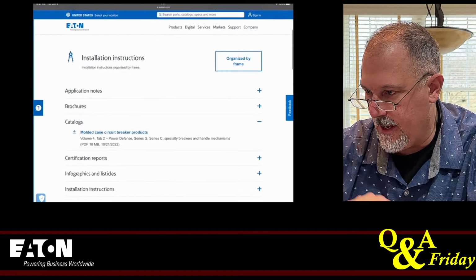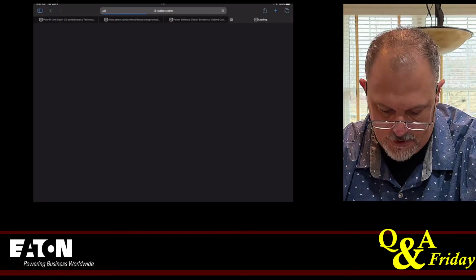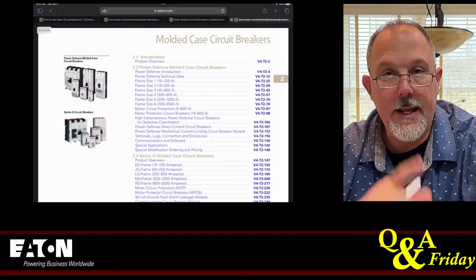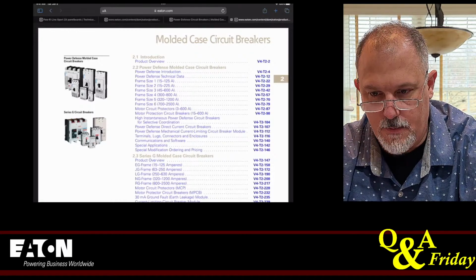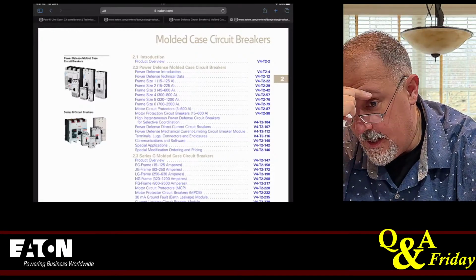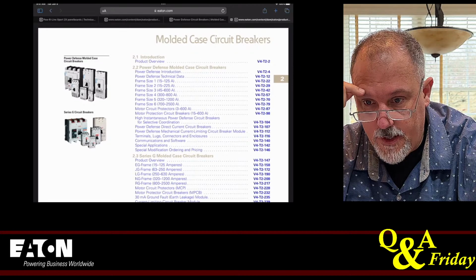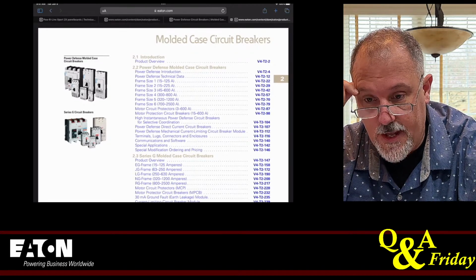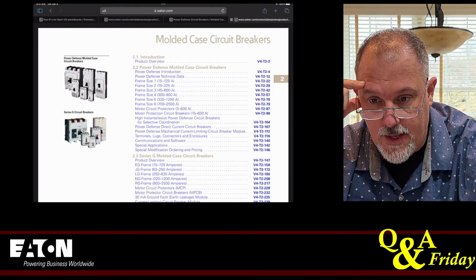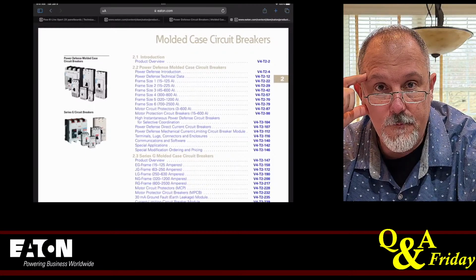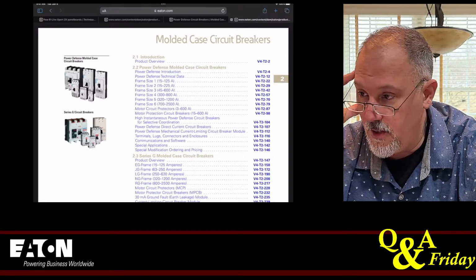All right, so let's look at catalogs, molded case circuit breakers. What breaker would I use? I talked about this before. Yeah, a 225 amp can only take one conductor per phase, so I would do the 4-aught. Thank you, Alan. So a 4-aught conductor, that's what I would do on the secondary.